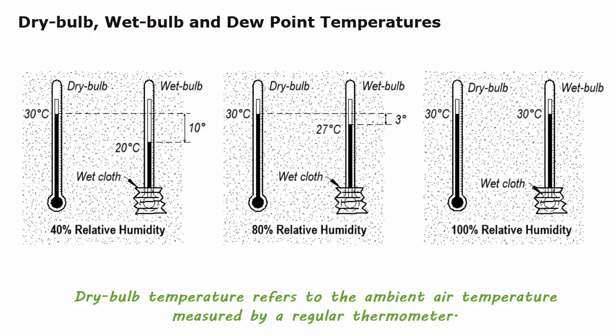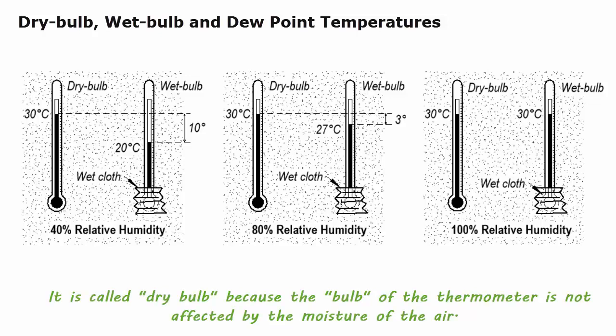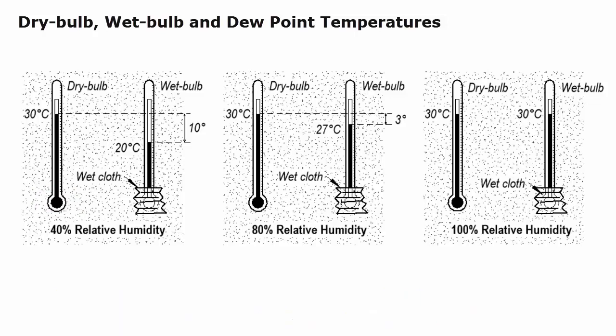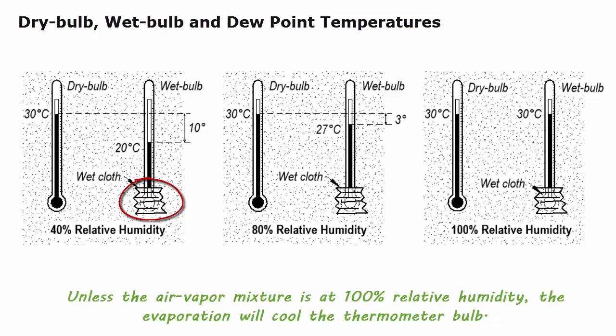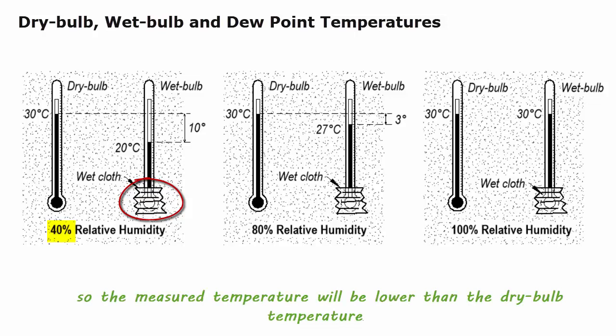Dry bulb temperature refers to the ambient air temperature measured by a regular thermometer. It is called dry bulb because the bulb of the thermometer is not affected by the moisture of the air. Wet bulb temperature measures the effect of moisture by using a thermometer with its bulb covered by a white cloth. Unless the air-vapor mixture is at 100% relative humidity, the evaporation will cool the thermometer bulb, so the measured temperature will be lower than the dry bulb temperature.